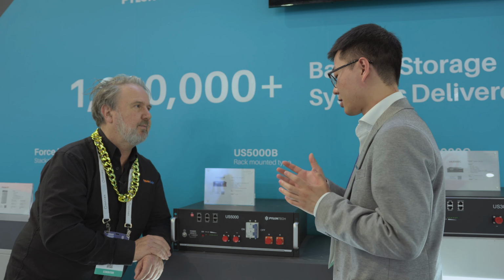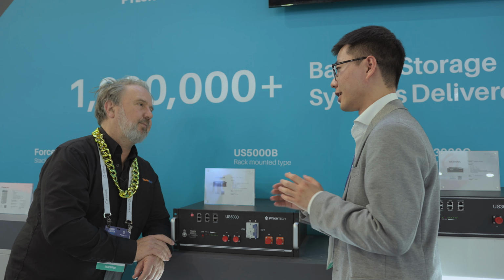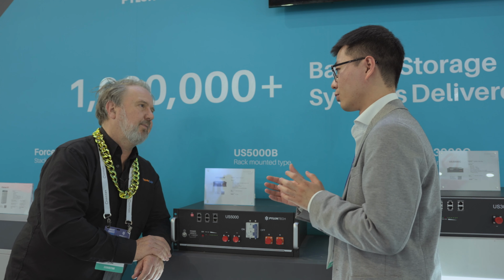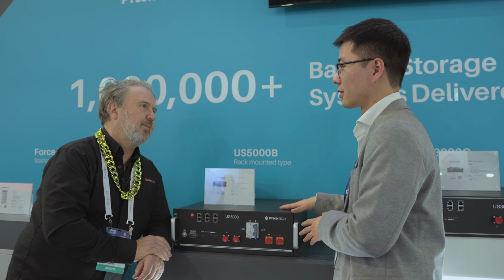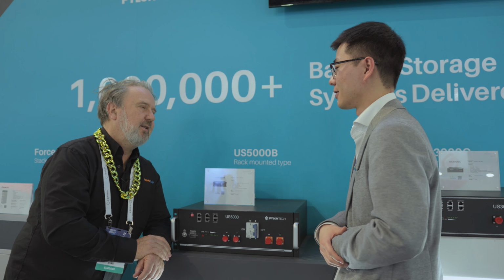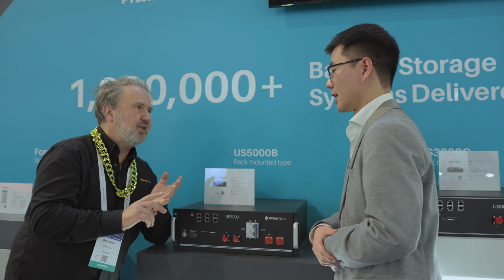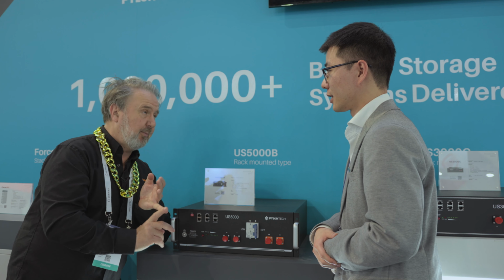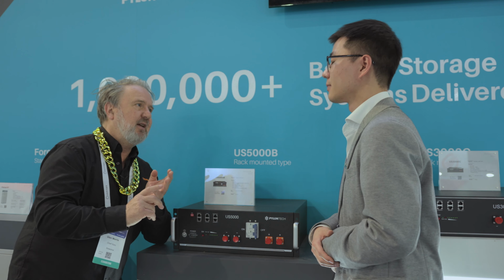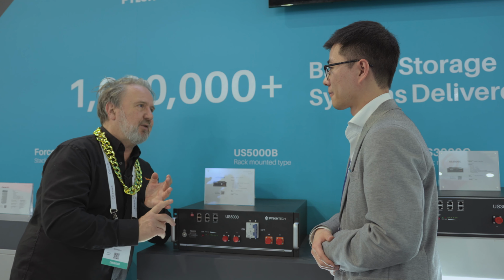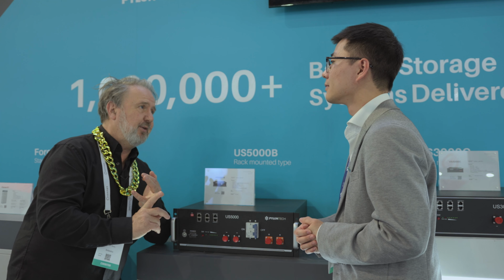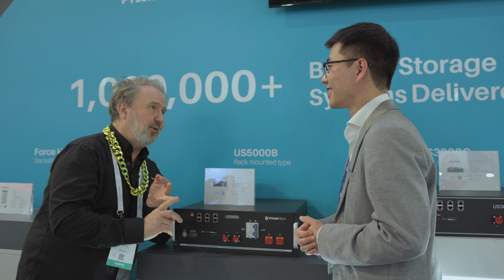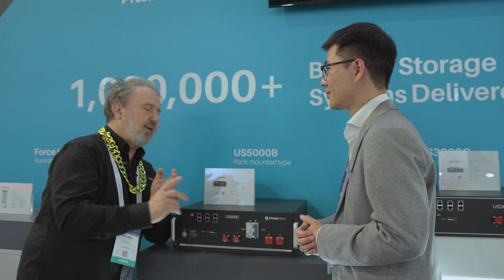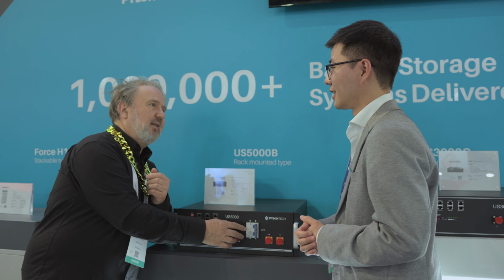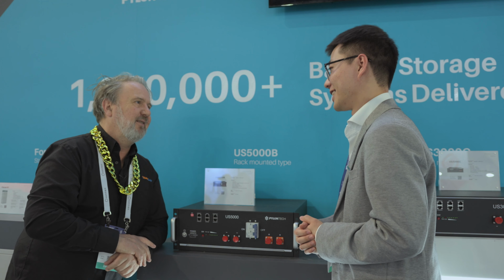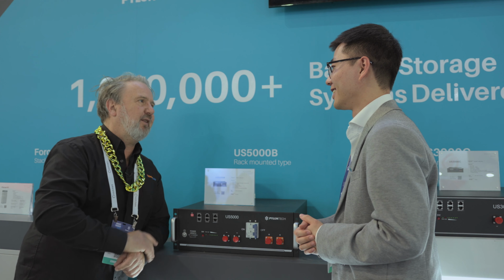So the installer or customer doesn't need an external DC breaker to protect the battery system. We have our own protection, so that's 3 levels of protection. So you've got a semiconductor switch, a MOSFET, controlled by the BMS. If for any reason the BMS fails, you've got an inbuilt fuse which will just trip without any control. And you've also got string overcurrent protection externally with your circuit breaker, which helps with Australian standards. Yes, exactly. So you can parallel a lot of these together.